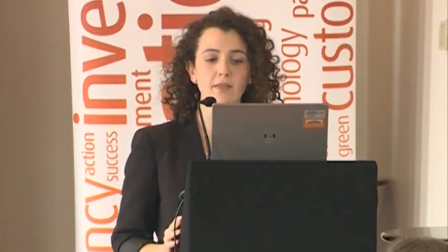Now, in the case of that happening, our generators would probably benefit because UK Power Networks would take on that reinforcement, and the generators could probably come back and say, I want to reevaluate my connection, or see if now I'm in a position to not have an interruptible connection, and we'll probably have to deal with that at that time. And then there is generation-triggered reinforcement. It would come a moment when an extra generator requests a connection there, and the minimum cost scheme at that point would actually be reinforcing the network. That would be the case in which we would drive reinforcement triggered by generation.